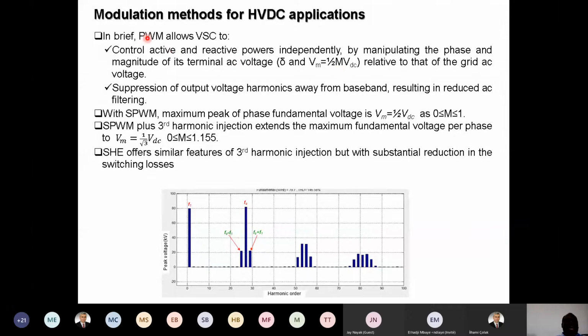And also PWM helps the VSC to suppress the harmonics far away from the baseband. If you see here, this is the spectrum, this is the fundamental. The integer multiples of the fundamental we call baseband frequencies. You can see here there's no second, no third, no fifth. So all this baseband is clear when we use PWM. The first group of harmonics we'll have in a VSC is at the switching frequency and its sidebands, and sometimes we call them interharmonics in power systems. So the higher the switching frequency, the farther this group is from the fundamental, and then it's easier to filter them out, and so on.